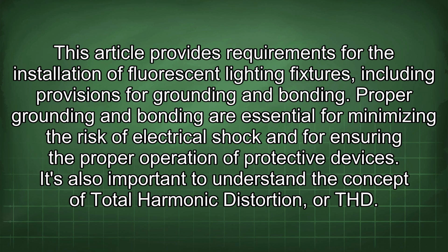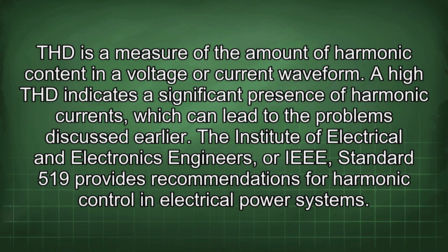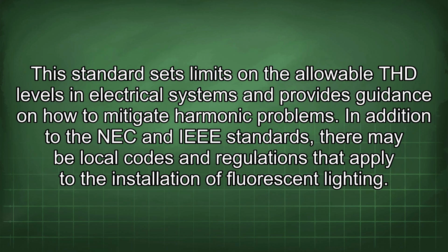protective devices. It's also important to understand the concept of total harmonic distortion, or THD. THD is a measure of the amount of harmonic content in a voltage or current waveform. A high THD indicates a significant presence of harmonic currents, which can lead to the problems discussed earlier. The Institute of Electrical and Electronics Engineers, or IEEE, Standard 519 provides recommendations for harmonic control in electrical power systems. This standard sets limits on the allowable THD levels in electrical systems and provides guidance on how to mitigate harmonic problems.